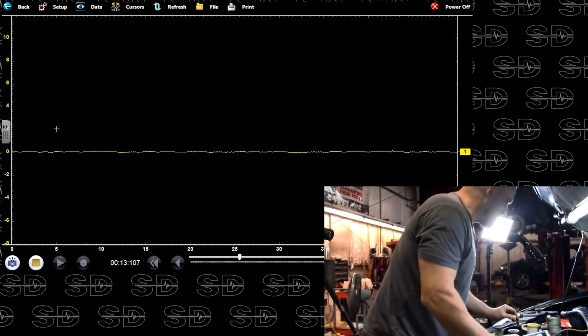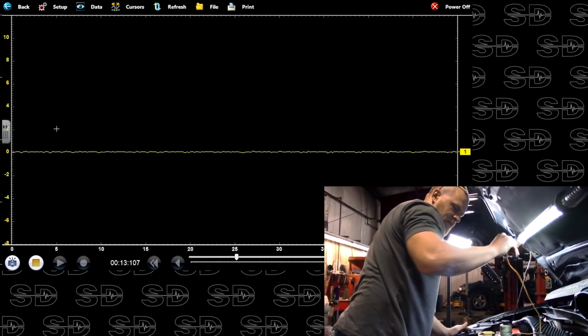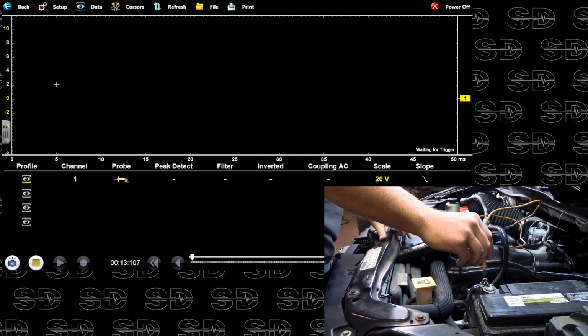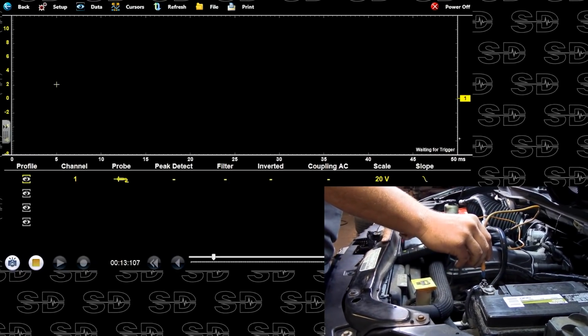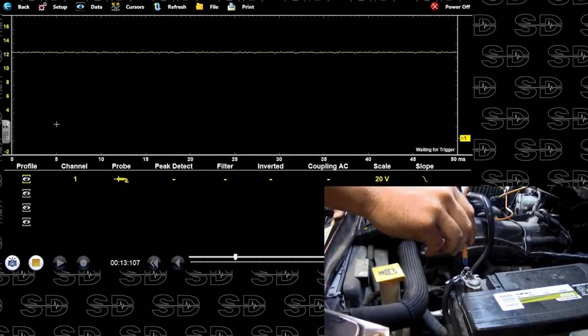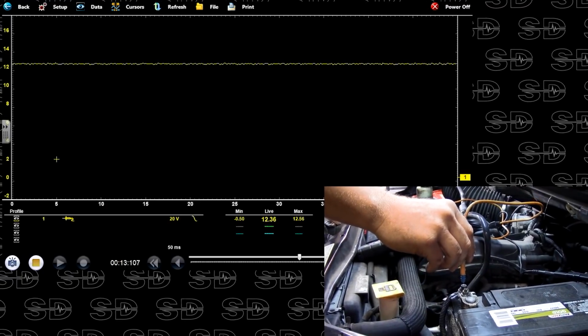Nothing on that wire, seriously? I've got no voltage on this purge valve. Let's make sure my lead works first. You always want to check your meter whenever you get weird readings. See, I'm reading 12.3 volts.